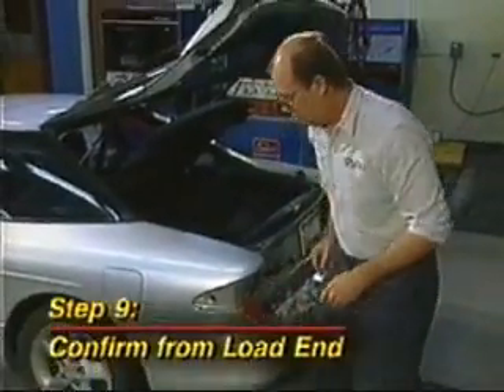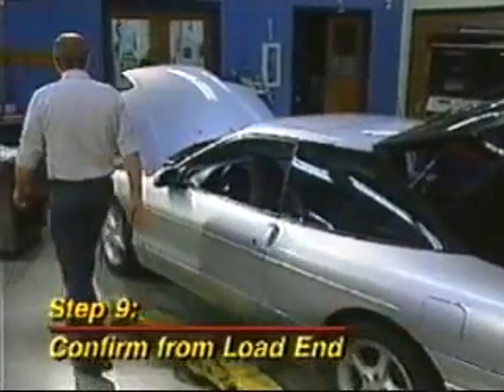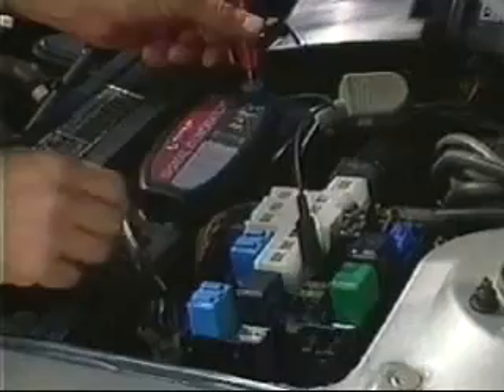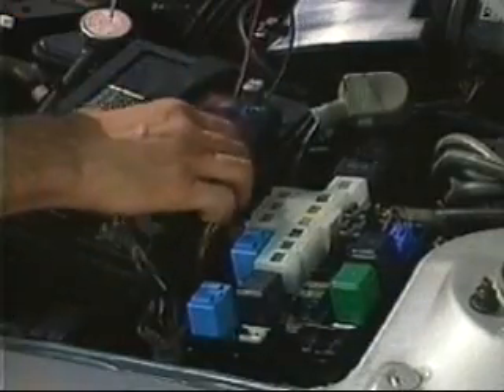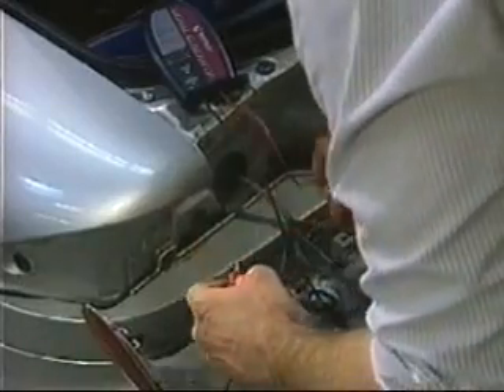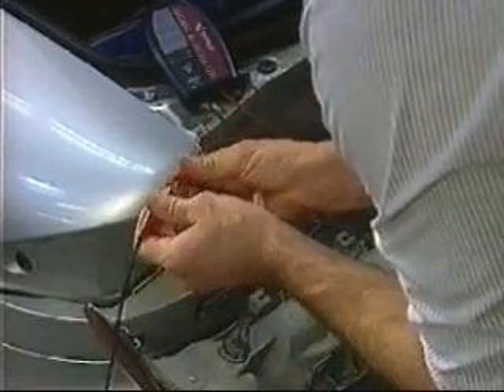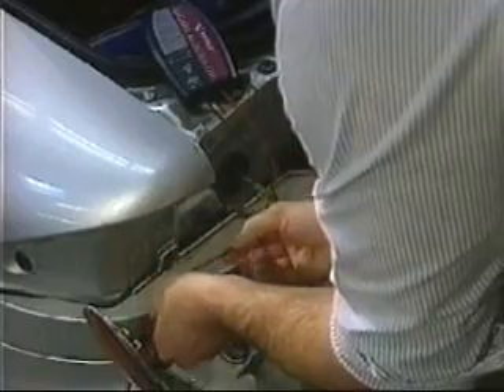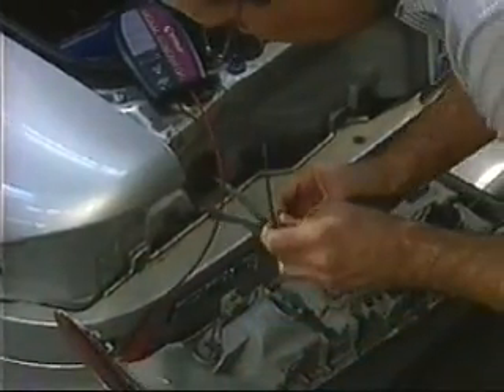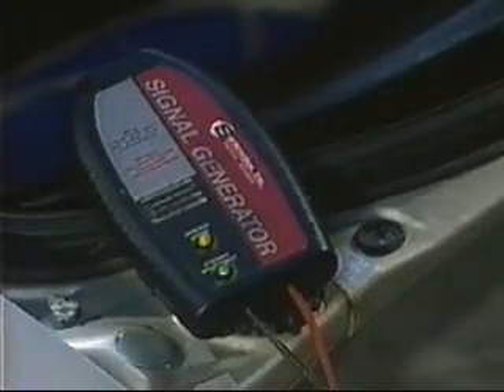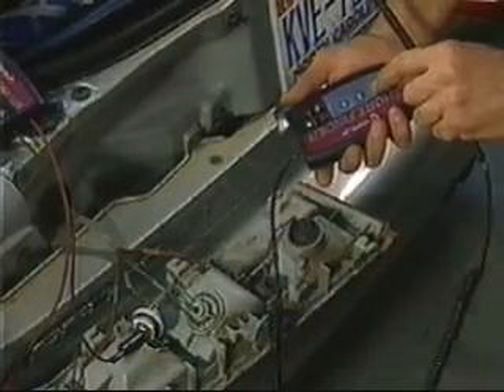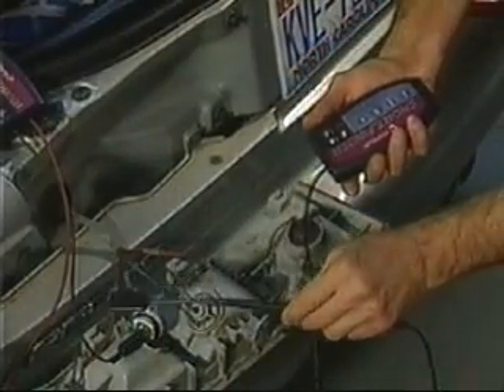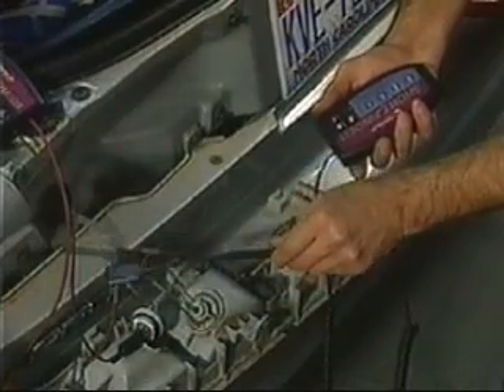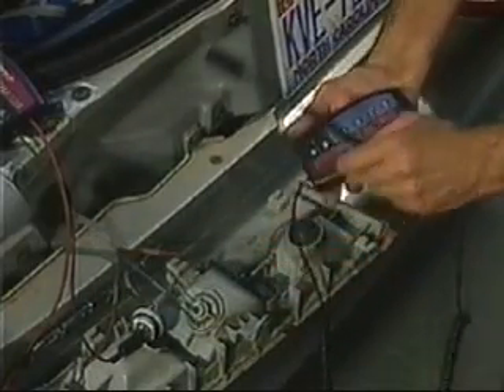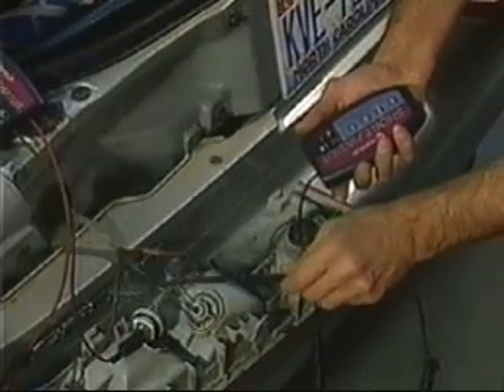Step 9 is to confirm the location of the short by sending the signal from the load connection on the other side of the short. Disconnect the signal generator from the load side of the fuse block and reconnect it at the load connection. Check to make sure that both lights are lit on the signal generator, indicating that you are electrically connected to the short again. Use the receiver to trace the signal from the signal generator back to the short location. The signal should stop at the same place as before, confirming that you have located the short.